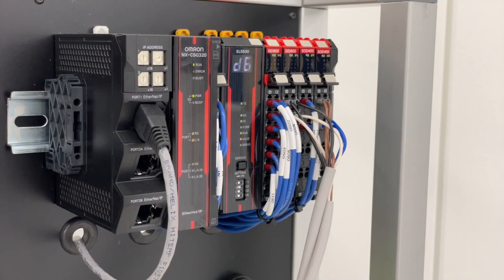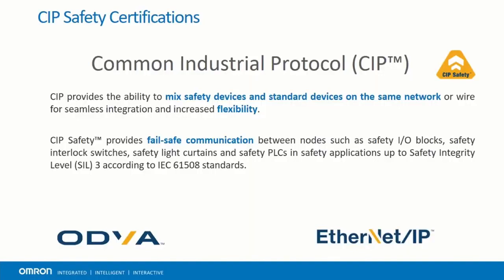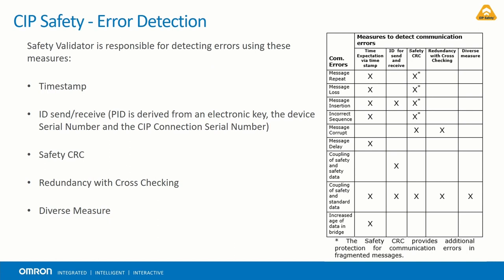One of the safety networks that the NX-SL5500 uses is CIP Safety over EtherNet/IP. CIP Safety, also known as Common Industrial Protocol Safety, is a TÜV-certified extension added to the CIP application layer to provide safety services on CIP-based networks such as DeviceNet and EtherNet/IP. CIP Safety allows for multicast messages, which decreases response time. By making end devices responsible for ensuring the integrity of data, there is no need for special communications software or hardware, because safeguards are in place to protect the data.